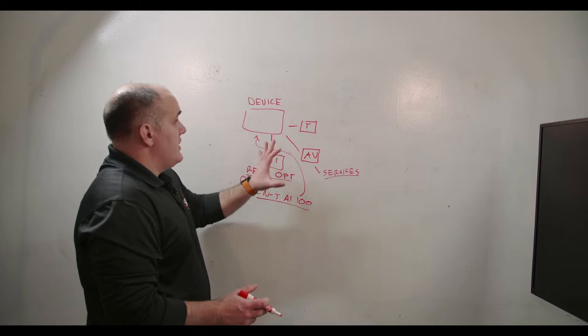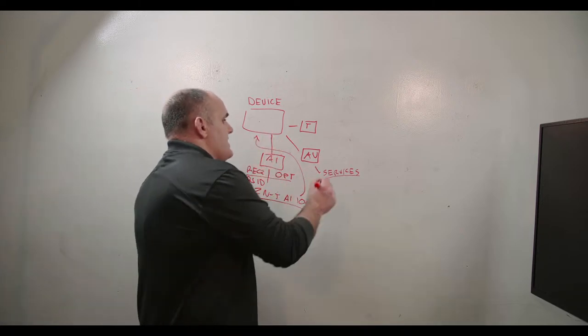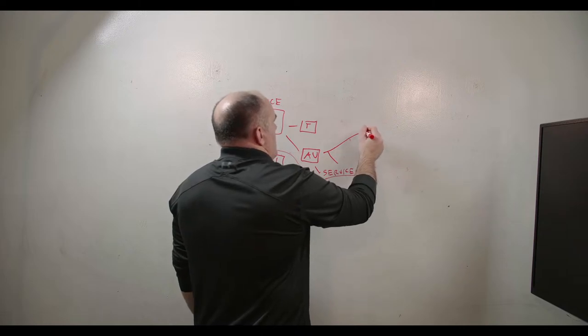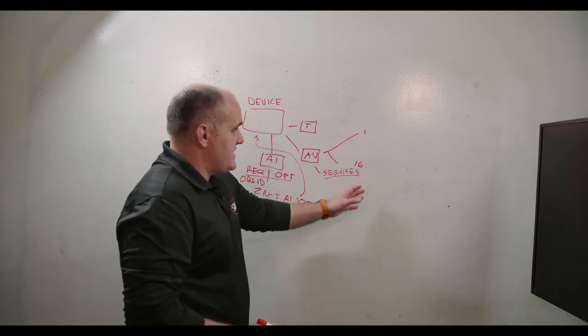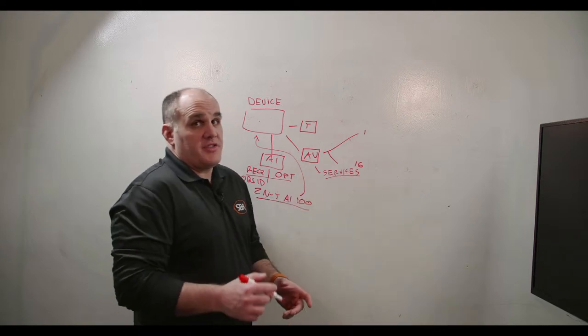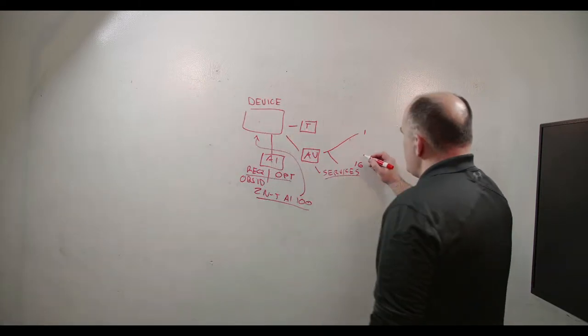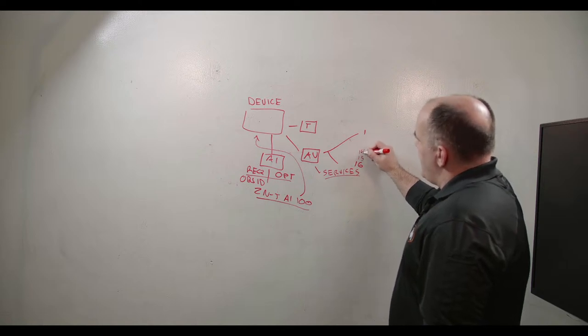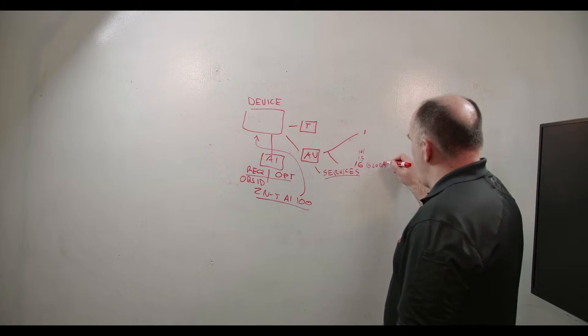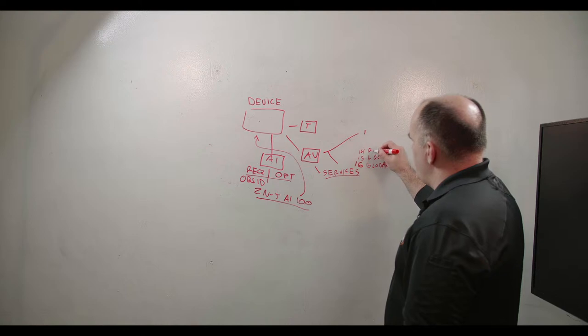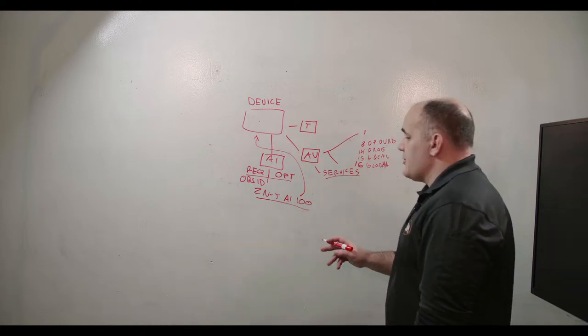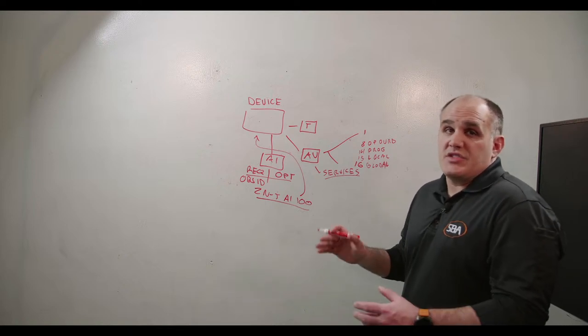It's kind of like private networks and subnetting, where you can have multiple 192.168.1.x subnets as long as they're nested under unique public addresses. Now, the priority array is a 16-element array going from 1 to 16 — 16 being the least important, 1 being the most important. When you write to an object you can choose which priority to write to. For example, 16 might be global, 15 local, 14 programmatic, and 8 operator override.